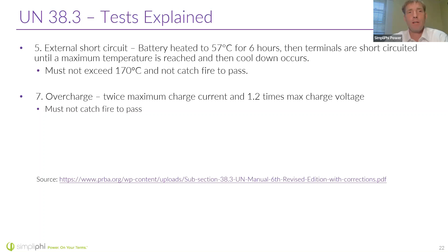Overcharge: we charge the battery 1.2 times what it should be, going above the max charge voltage, and again, it must not catch fire. This is what goes into this test, and this is why only certain batteries are approved for transport. So if you are transporting batteries, before you take them to the airline, make sure they're approved like our SimpliPhi batteries are. If you have any questions about that, feel free to contact us before transporting — we'll let you know which batteries are safe, etc.